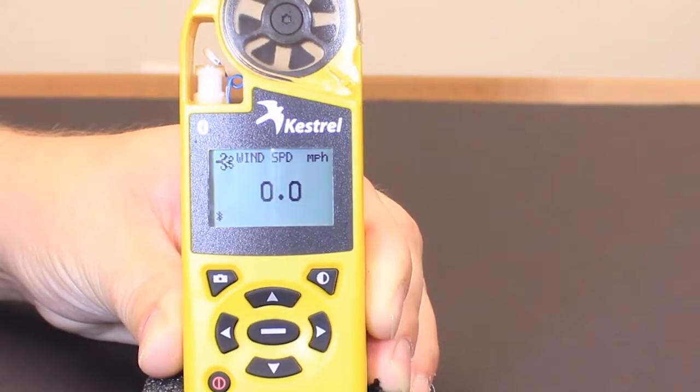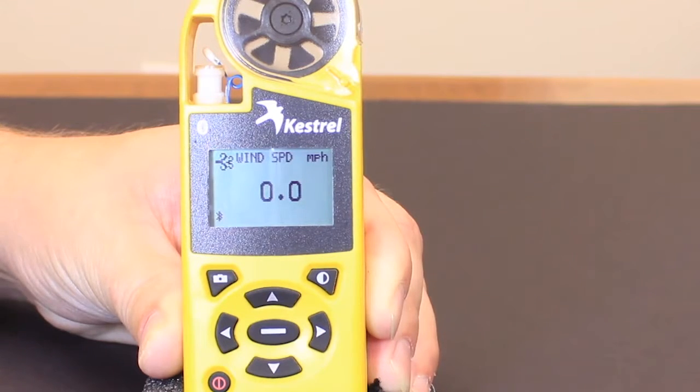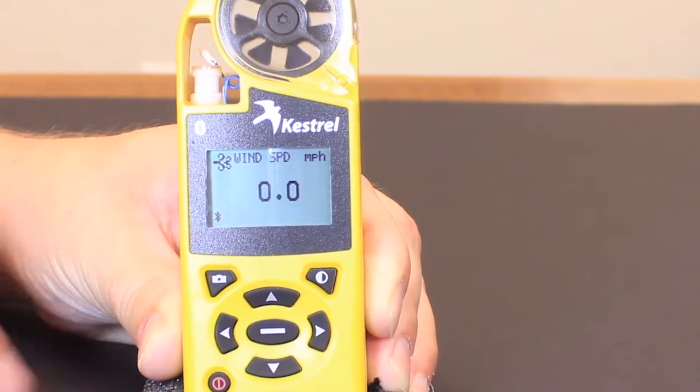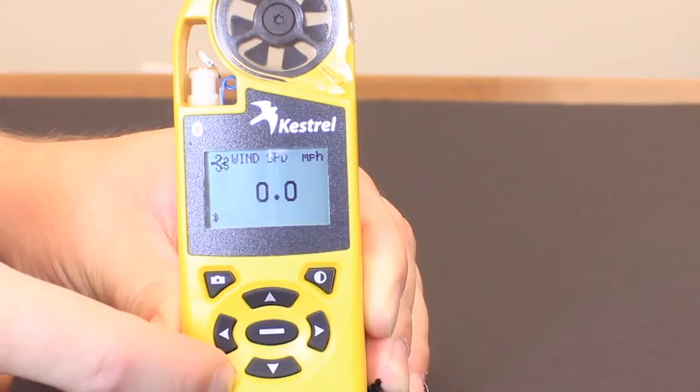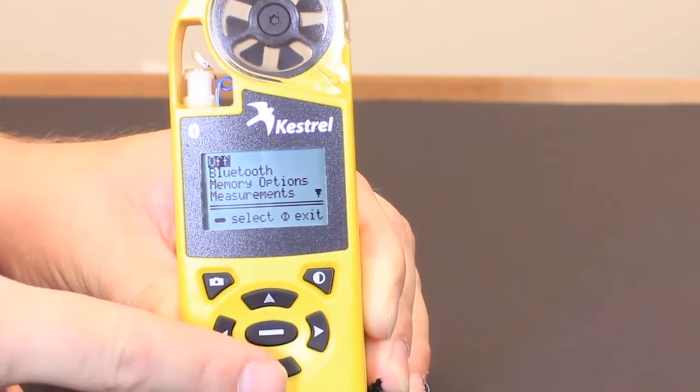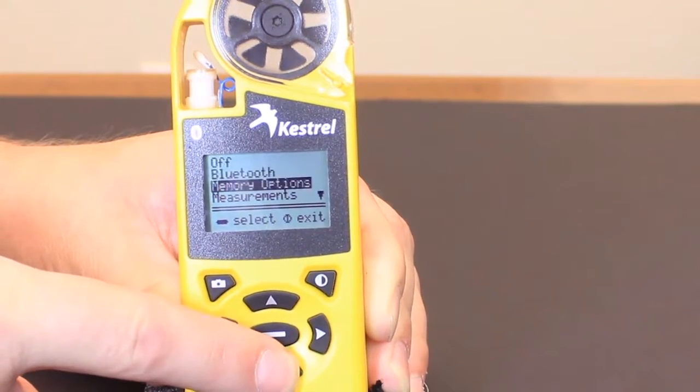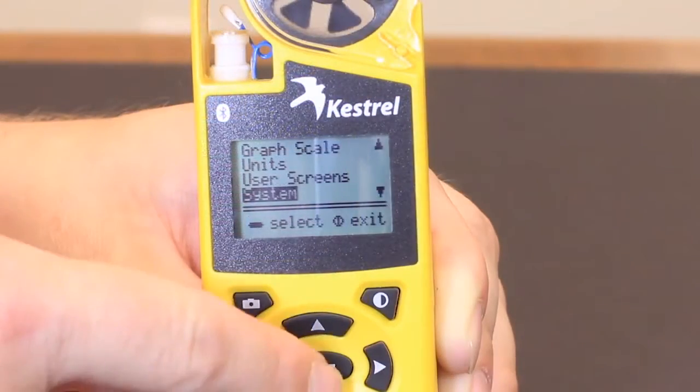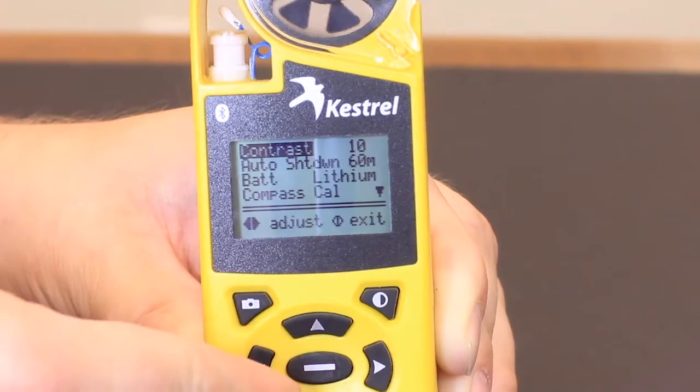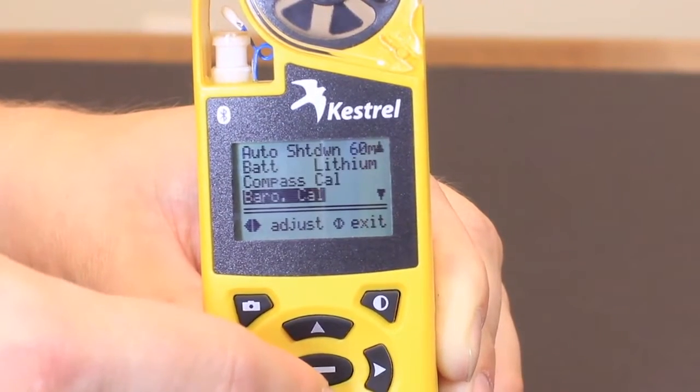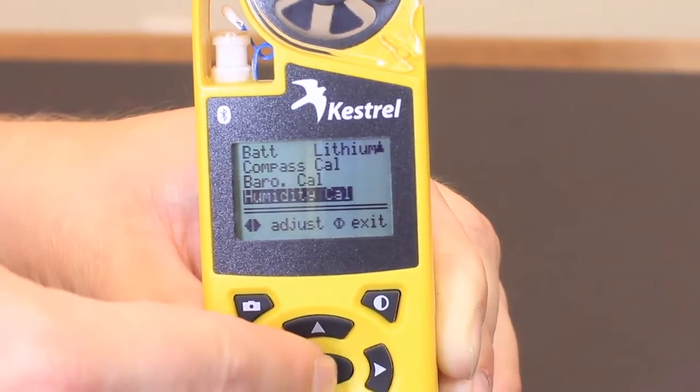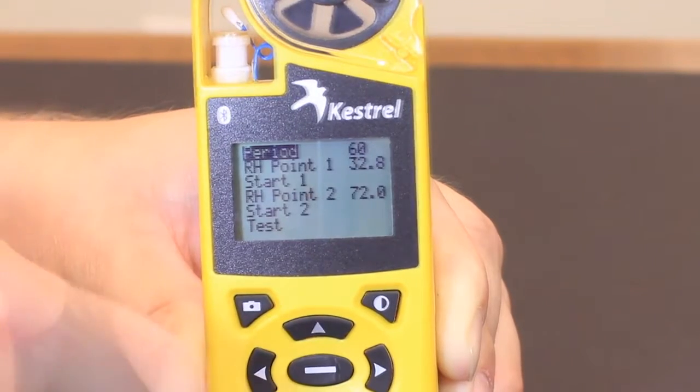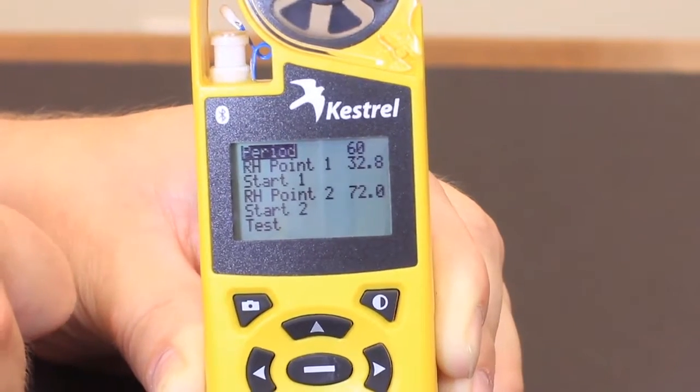In order to calibrate the humidity on the Kestrel 4000 series, you'll turn the unit on and press the power button to get to the main menu. You will scroll down until you see 'system.' Press the center button to enter the system menu and scroll down until you see 'humidity cal' and hit the center button. The period is going to be 60. That's the amount of minutes that you want to leave it in each chamber, so do not change that.